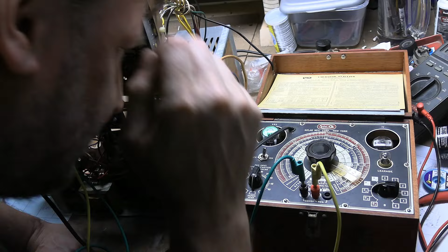See, I can't test for capacitance. It's not giving me a distinct eye, which is a good indicator that it has a problem. On the 3 range it should read right around here, and I'm just getting around 0.003, or 25 - I'm getting a hazy indication in the eye. It should give a really distinct open pie wedge when you're on value, and I'm not getting that. So even though I can't test at the full rated voltage, and it's not showing leakage at 500, the fact that I can't measure the value is not a good sign. So I think it does need to go.